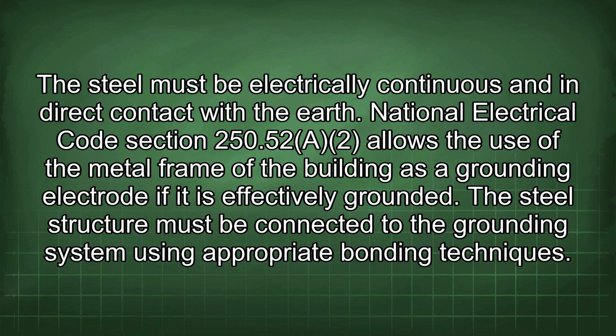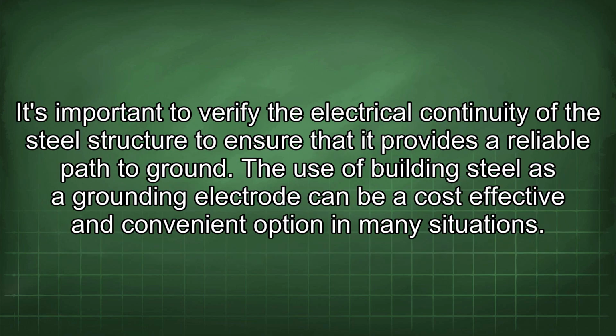The steel structure must be connected to the grounding system using appropriate bonding techniques. It's important to verify the electrical continuity of the steel structure to ensure that it provides a reliable path to ground. The use of building steel as a grounding electrode can be a cost-effective and convenient option in many situations.